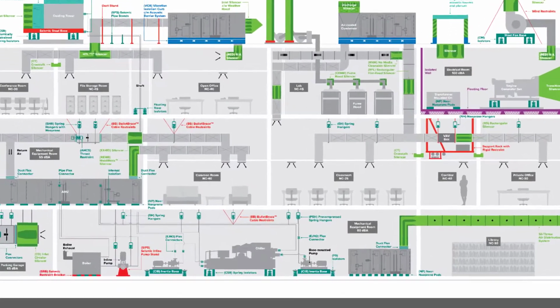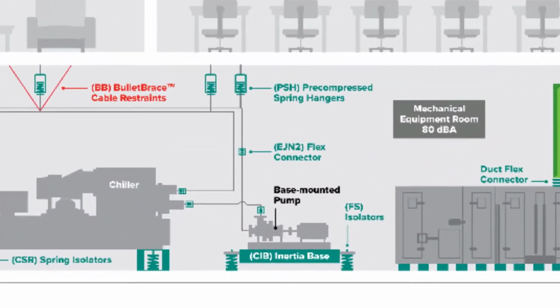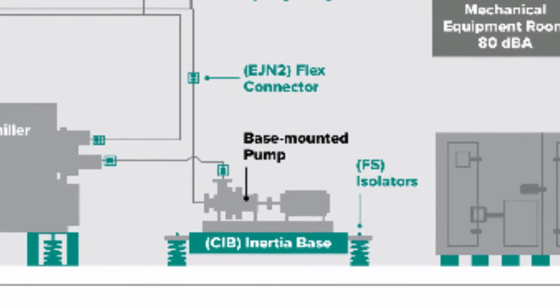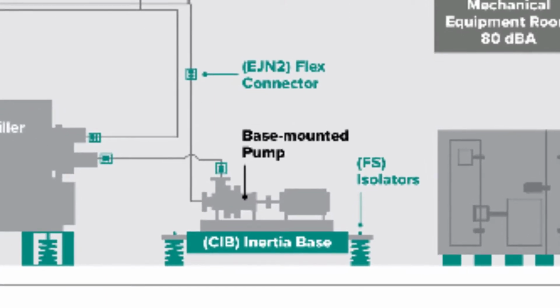Vibro-Acoustics creates noise control solutions for the HVAC industry, addressing both airborne and structure-borne transmission paths. Our vibration isolation products help mitigate equipment vibrations that could cause noise problems in buildings. In this lesson, we will look at concrete inertia bases on Type FS floor spring isolators supporting hydronic pumps.